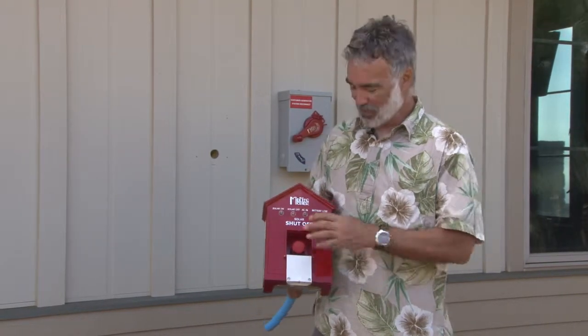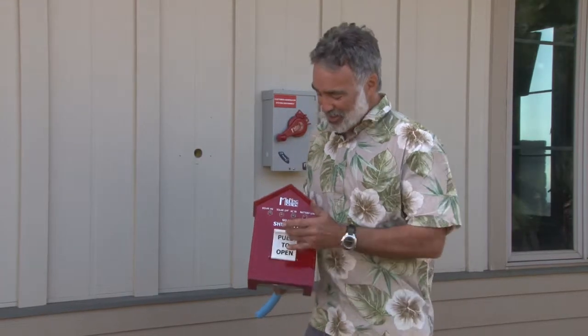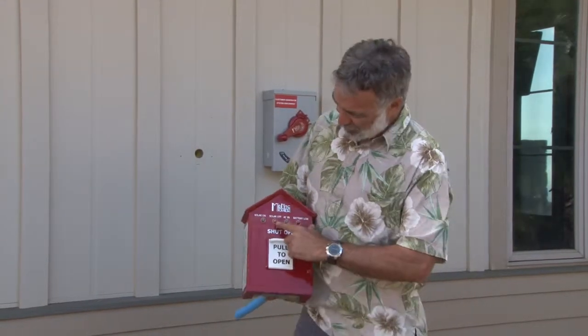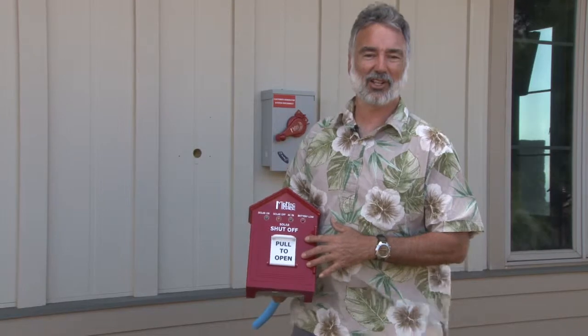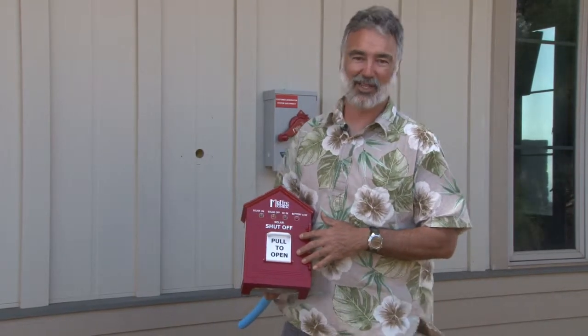Pushing the button will activate the Birdhouse, and it'll disconnect the combiner. It'll then tell you the solar is off, speaking to you in clear, plain English, telling you that the PV array is off and that there are no lethal voltages present below the array level.